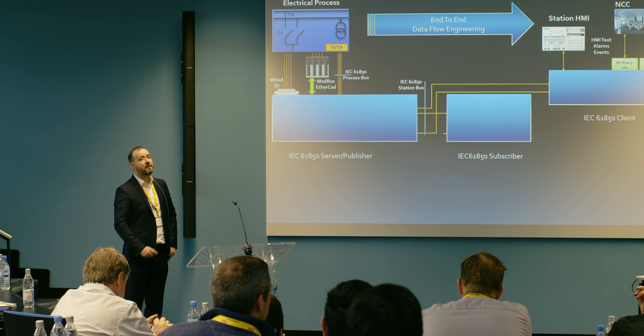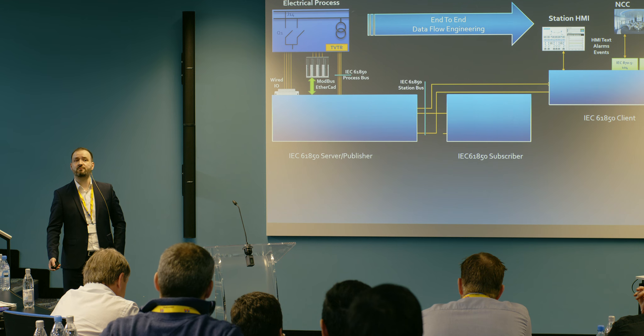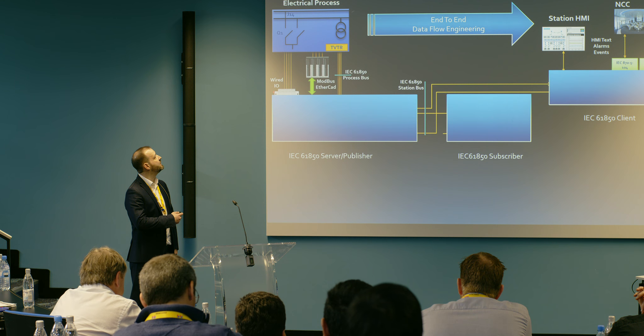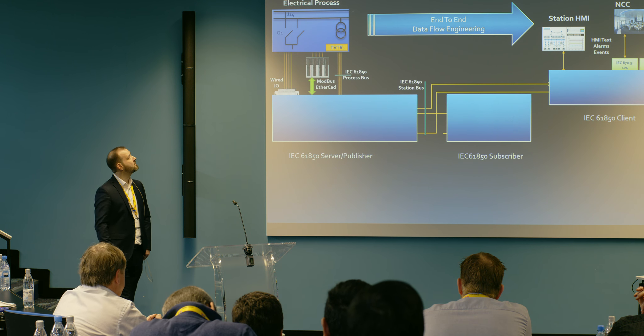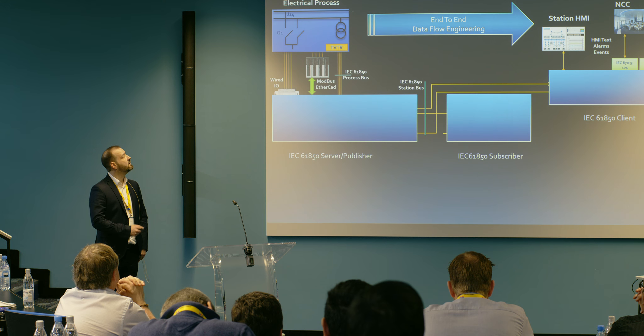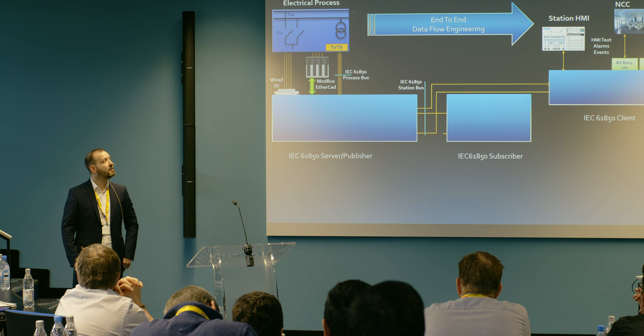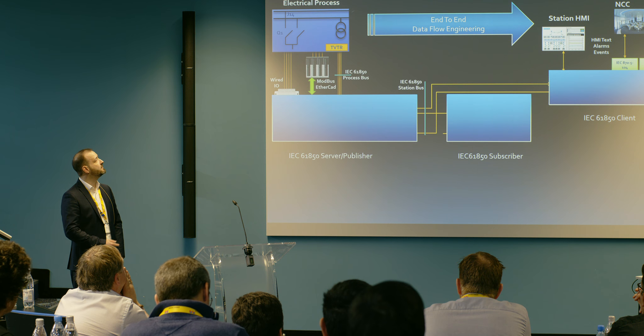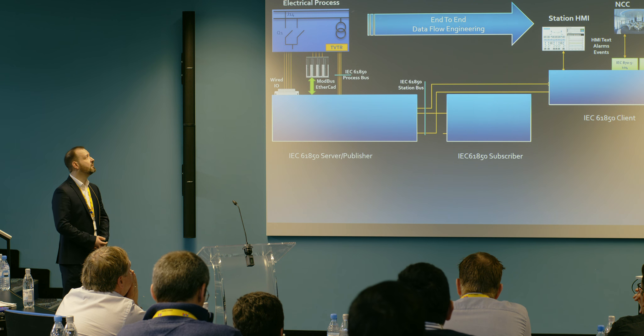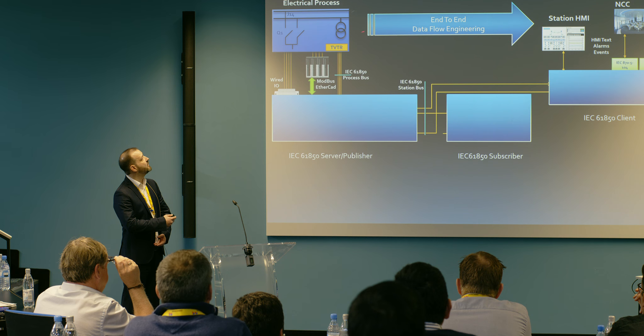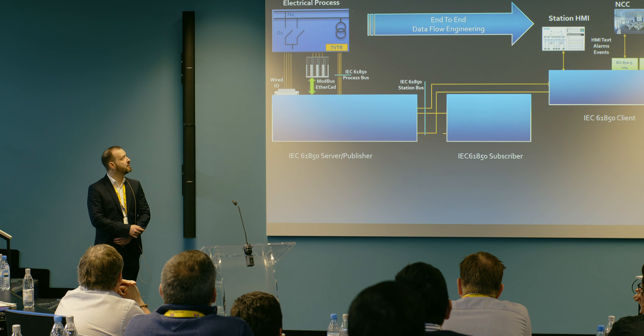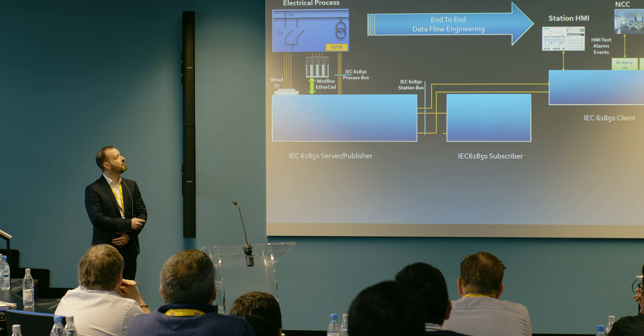All the way to the left we have wired I/O — actual wires that start at the primary equipment and end up in a terminal block in the device. There may also be devices that communicate via any fieldbus, such as Modbus or EtherCAT, which are information that is relevant to be received on the other end of the engineering. Finally, we may also have intelligent sensors that are already 61850-aware — for example, a voltage transformer publishing a sample value stream readable via the process bus.